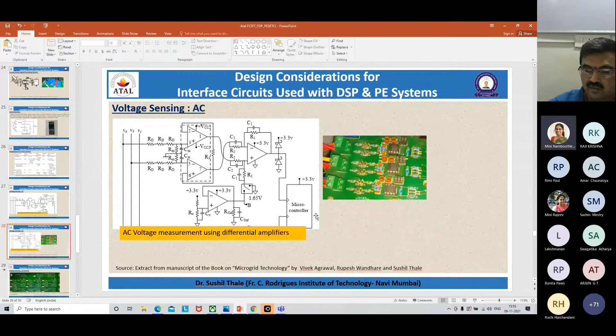This is differential voltage sensing by having high impedance coming into picture. There is no isolation, you can see this. In this case, phase A, phase B, phase C three-phase AC voltage have been connected directly to this high resistance ladder network and attenuated substantially, then given to the amplifiers directly. There is no isolation coming into picture. After appropriate filtering and amplification with clamping diodes, it is connected to the micro input. These are without isolation. In low-cost applications, you can always use non-isolated interfaces. The high resistance impedance network itself will act like an isolation barrier for the high voltage side and the low voltage side. So this is the picture of that.